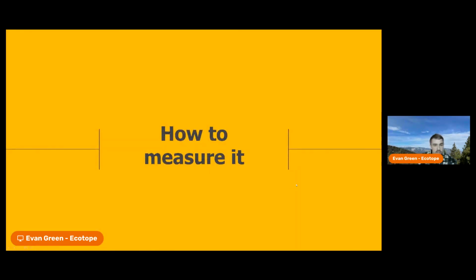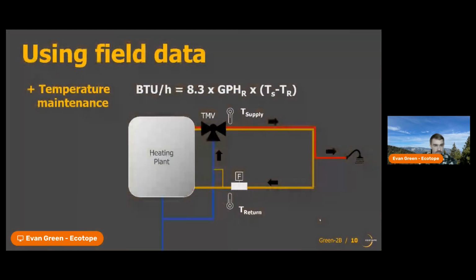So now that we've determined the difference between this temperature maintenance flow and this delivery flow and the heat losses associated with it, we can talk about how to measure these heat losses in an existing building. If we have the proper monitoring equipment in this building, we'll start by talking about measuring the temperature maintenance heat loss. And remember, that's the heat that's leaving this temperature maintenance loop as it circulates around.